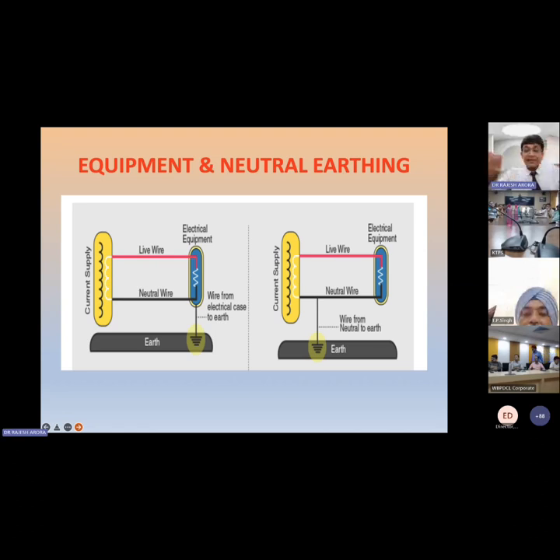When all these systems are there, there are three fundamental things you require. You need basic protection. You need some protection against fault. You need some additional protection. When I say protection, that is protection against electrical hazard, electrocution, protection against overvoltage, protection against overcurrent, protection against thermal effect, protection against lightning.